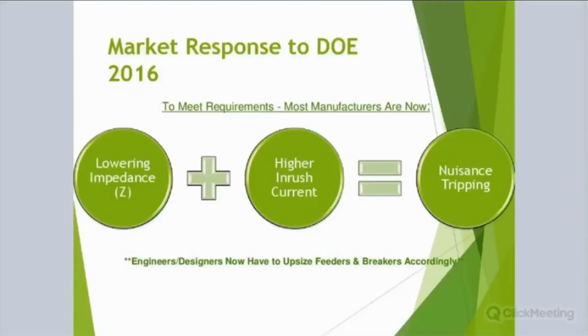There are issues with that. So there are ways to manufacture transformers and not have a low impedance or a high inrush. But again, typically by doing those designs, it's a more labor intensive construction, and typically the product costs a little bit more. So it just keeps going back to the higher performance is going to cost a little more, but the payback we'll touch on in a minute will show that it's well worth the little bit added cost up front to save you money over the course of the life of that unit.